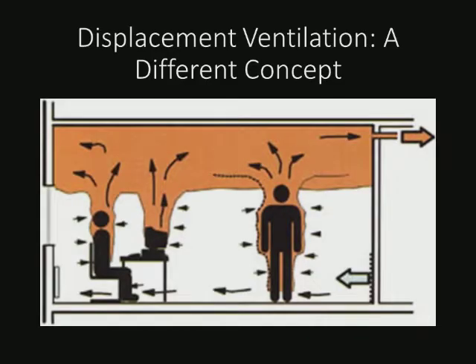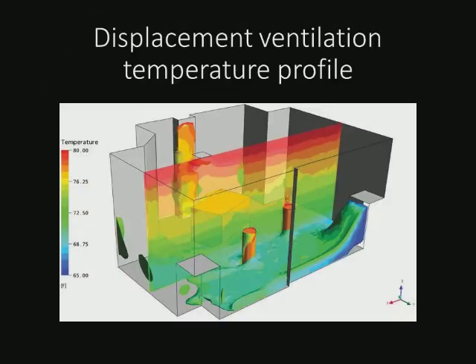For those not familiar, the theory behind displacement ventilation is to bring in your supply air at a low elevation and exhaust your air at a high elevation. This allows you to have less cooling load, a smaller coil, a smaller fan, and it stratifies the air inside the room so that we're only cooling the first 6 or 7 feet of air inside the building.